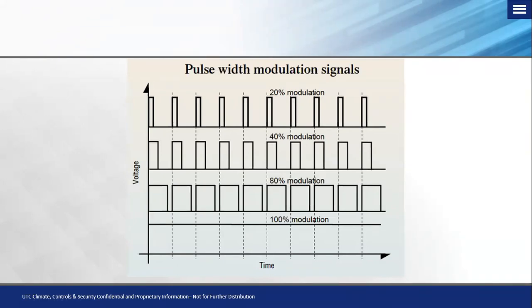Now again, that's based on pretty much every sensor that feeds back to that outdoor board, including the sensors on the indoor unit and positioning of different valves and compressor speed. So everything that the system is really reporting back to the board, the compressor is looking at to try to get to a speed that's going to make the most sense and be the most energy efficient while being able to meet the requirements of the customer who's trying to either heat or cool their space.